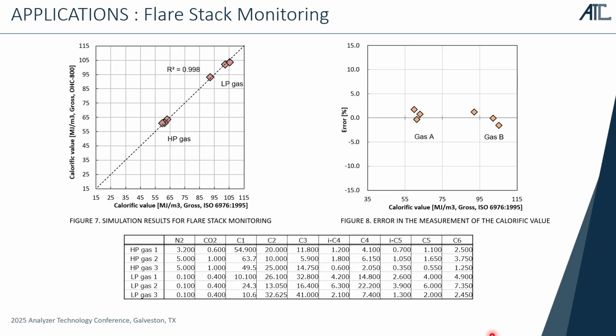And then the good thing on this application is the measuring range is quite wide. The optosonic sensor can measure 0 to 2800 BTU, which can cover the low pressure gas and the high pressure gas, both with the one sensor. So using the one sensor covered 2 types of target gases. That's a strong point of this principle.